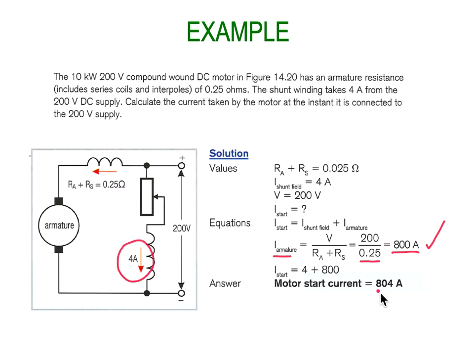Adding the shunt field current of 4 amps to the 800 amps armature current gives us a total start current of 804 amps. So to get this 10 kilowatt motor up and running takes 804 amps at start, before any back EMF has initialized and reduced our current. That's going to take a fair bit of thinking about.